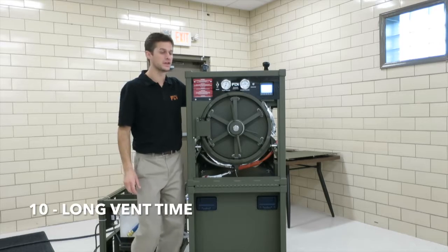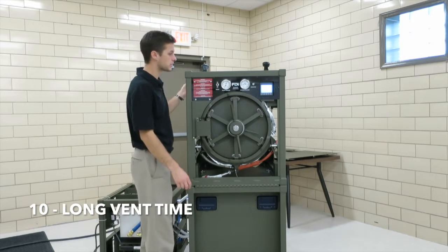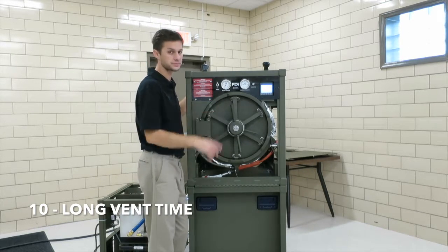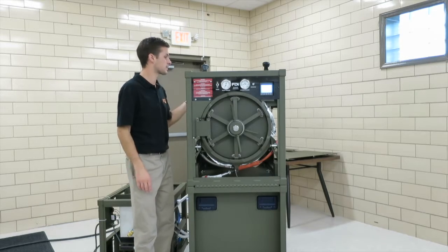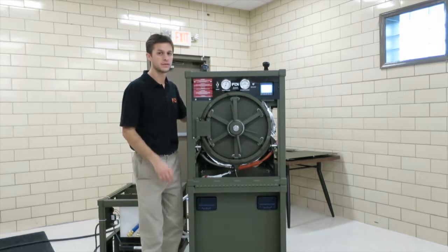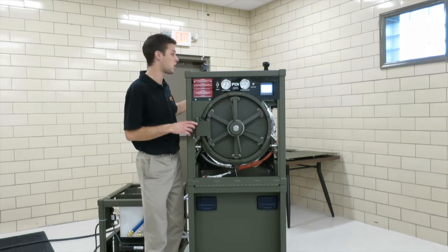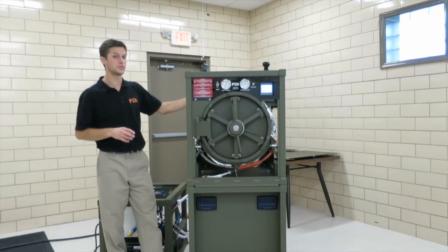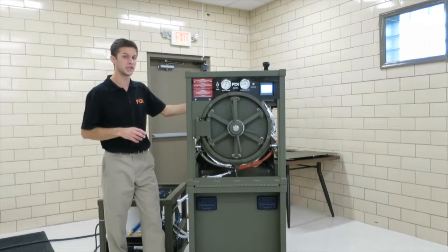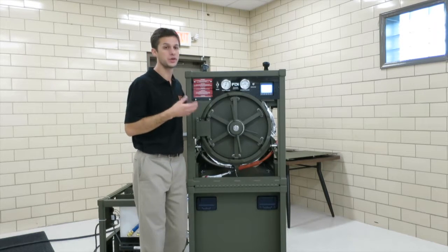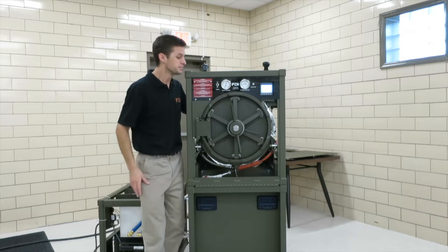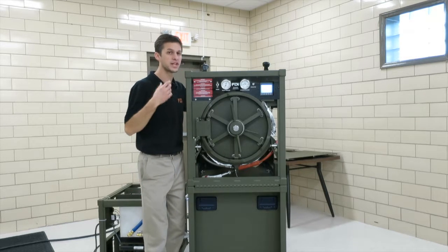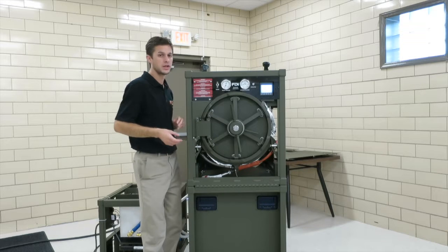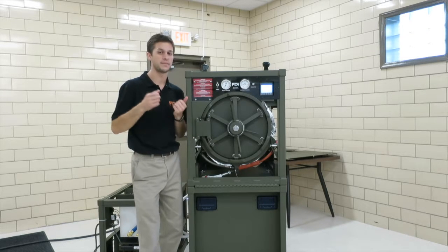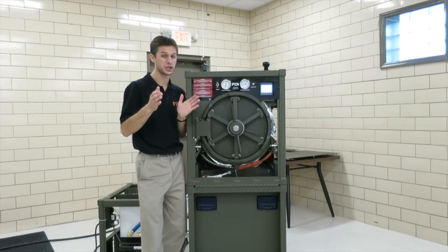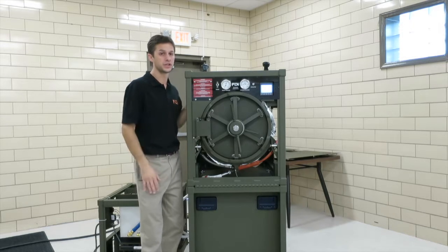Number 10 is a long vent time. So at the end of cycles, when the chamber is venting, if say the vent was clogged, the HEPA filter was clogged, if the vacuum break valves were not opening sufficiently, it could take a lot longer than normal to vent the chamber. And if it takes longer than normal, there's a watchdog timer kind of checking on the vent time, and it knows it should take a certain amount of time. If it takes longer than that, you'll get this long vent time.